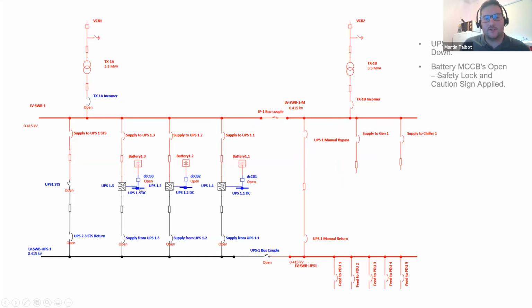We want to isolate the batteries as well, because they're a possible connection onto the main switchboard that we want to isolate. And also batteries are another hazardous area, which could produce not just electric shock, but an arc flash hazard. We need to make sure that we understand what that risk is and have we provided the correct personal protective equipment to deal with that.